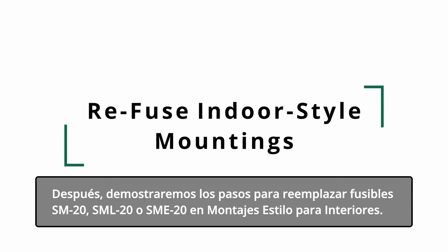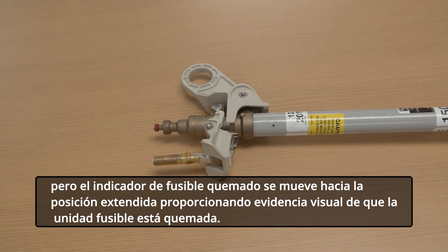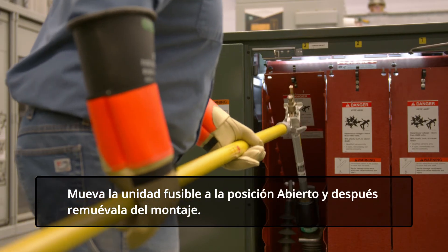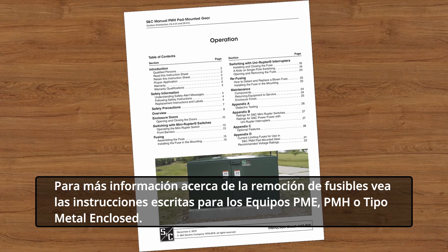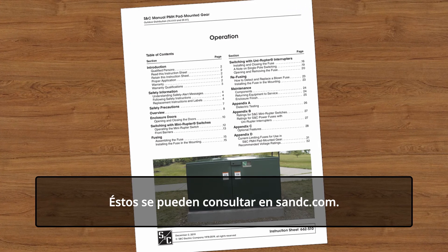Next, we'll demonstrate the steps to replace or refuse SM20, SML20, or SME20 indoor-style mountings. When the fuse operates, the fuse unit does not swing open, but the blown fuse indicator moves to the extended position, providing visual evidence the fuse unit is blown. Move the fuse unit to the open position and then remove it from the mounting. For more information on removing fuses, see the written instructions for PME, PMH, or metal-enclosed gear. These can be found at sandc.com.